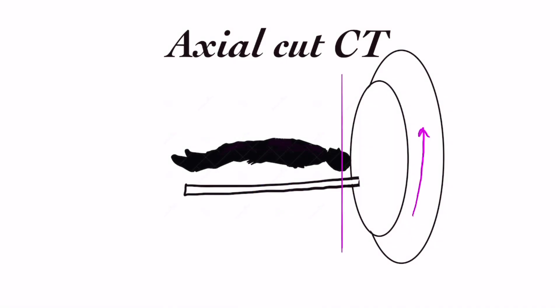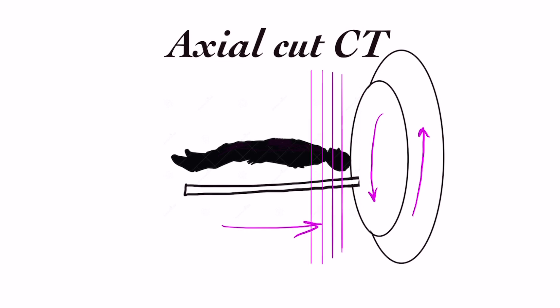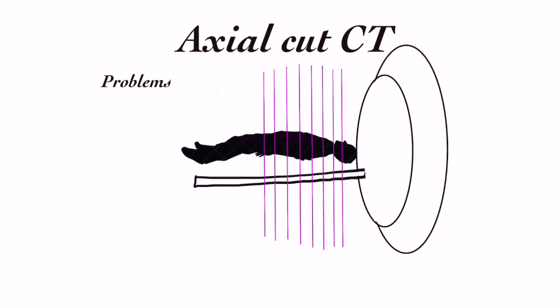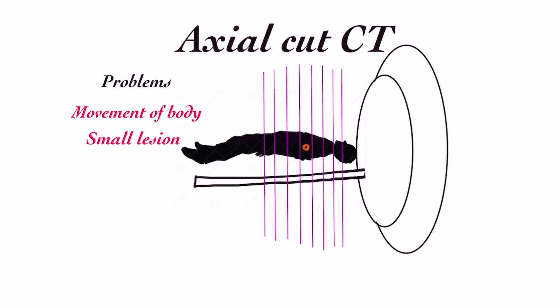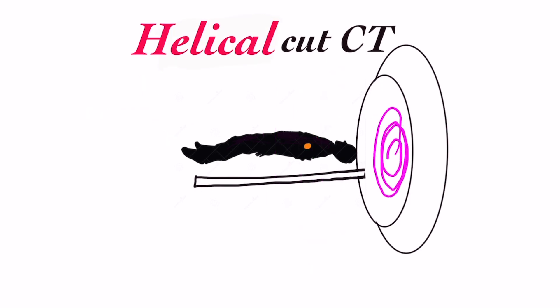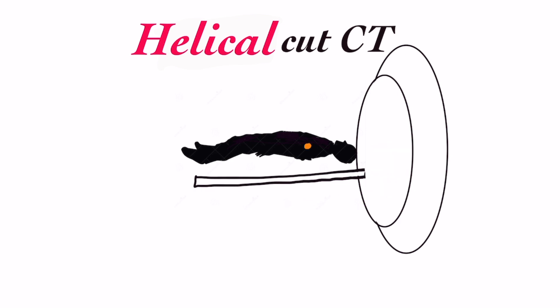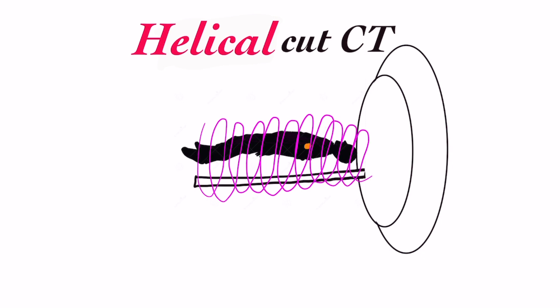In the axial method, a slice is taken with one gantry rotation; the machine moves a fixed distance and then another slice is taken, resulting in parallel slices of cross-sectional imaging. There are two problems with axial imaging: first, the body can slightly move between two slices, and second, a small tumor can lie between two slices and get missed — for example, a 5–6 mm tumor can lie between two 1 cm slices and be completely missed. Helical CT takes continuous sections while the gantry keeps rotating and the body keeps moving, resulting in faster imaging with decreased chances of any small tumor getting missed.